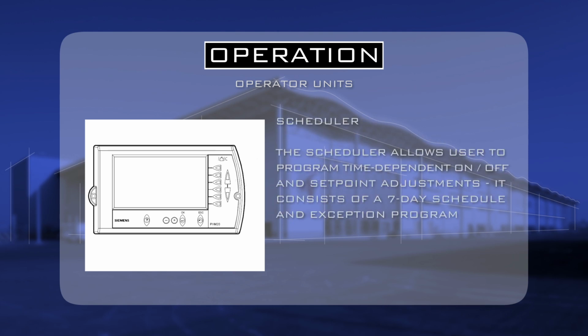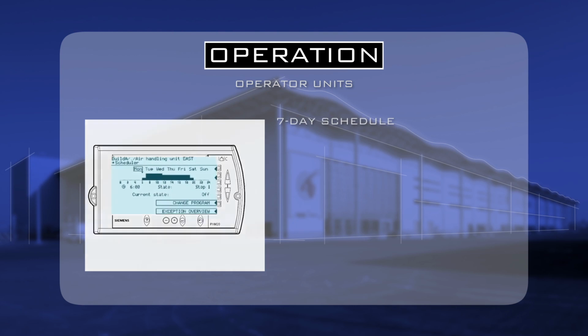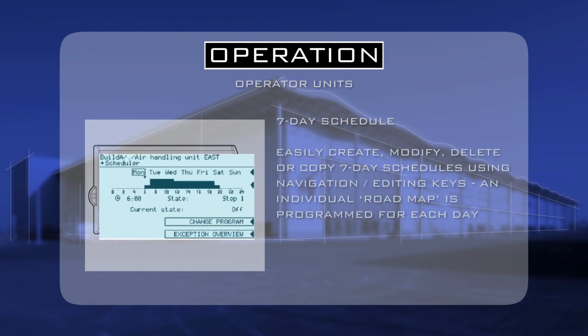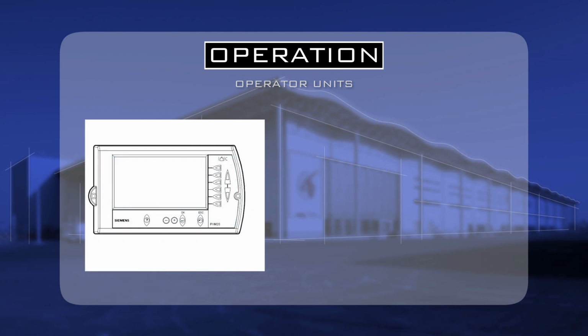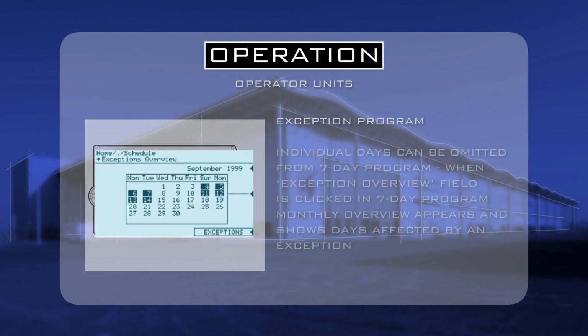The scheduler allows the user to program time-dependent on and off and set point adjustments. It consists of a 7-day schedule and exception program. You can easily create, modify, delete or copy 7-day schedules using the navigation and editing keys. An individual roadmap is programmed for each day. Individual days can be omitted from the 7-day program when the exception overview field is clicked. In the 7-day program, monthly overview will appear and show the days affected by the exception.